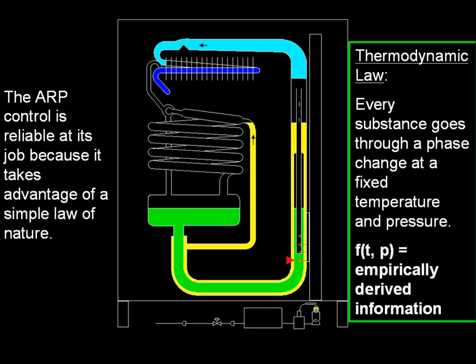The ARP control is reliable at its job because it takes advantage of a simple law of nature: the thermodynamic law that every substance goes through a phase change at a fixed temperature and pressure. The analogy to this is that at sea level, water boils at 212 degrees Fahrenheit. And as one raises altitude, the pressure goes down — therefore, the point of boiling goes down, so it takes longer to cook food.